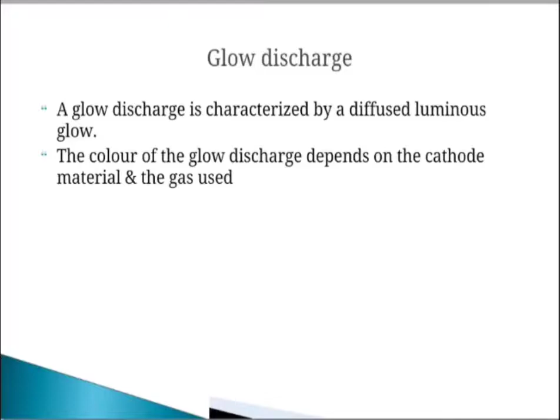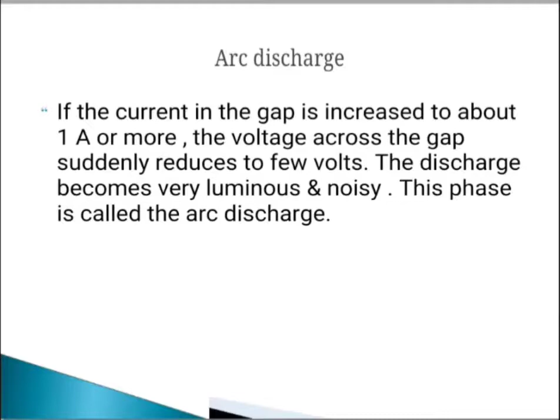The second one is the arc discharge. If the current in the gap is increased to about 1 ampere or more, the voltage across the gap suddenly reduces to a few volts. The discharge becomes very luminous and noisy. This phase is called arc discharge, and the current density over the cathode region increases to a very high value, 10 raised to 3 to 10 raised to 7 ampere per square centimeter. The arcing is associated with high temperature ranging from 1000 degrees Celsius to several thousand degrees Celsius. The discharge contains a very high density of electrons and positive ions, called the arc plasma. The study of arc is very important in the study of circuit breakers and switch contacts, so we have to know what the arc discharge is.